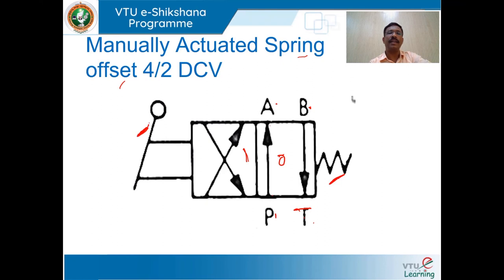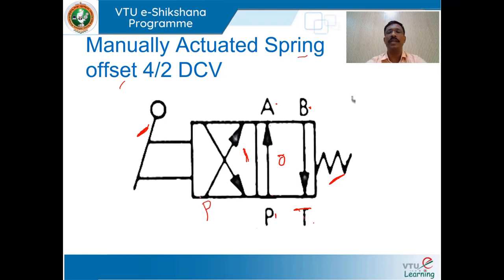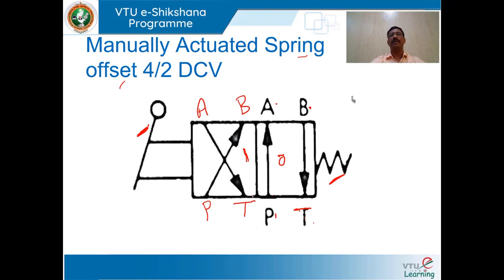When you operate the lever, the valve moves to position 1 and the spool slides within the valve body causing port opening and closing — P connects with B and A connects with T. This is how to draw a symbol for a manually actuated spring-offset four-way two-position directional control valve.